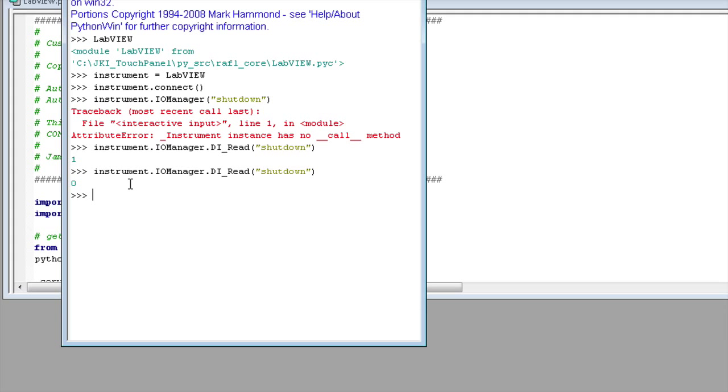And we find that, for example, mechanical engineers who maybe need to do a burn-in test. Maybe it's not a power button, maybe it's a door sensor on the instrument. They'll basically write a script that opens and closes the sample tray overnight, and they log the state of the door sensor or the sample tray sensor every time they do it, and they just want to do a burn-in characterization.